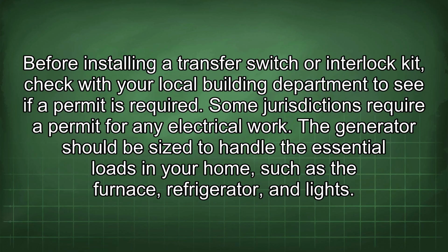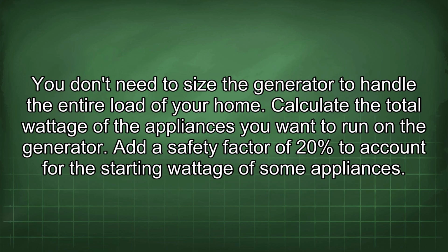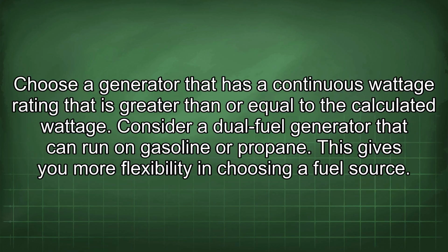Before installing a transfer switch or interlock kit, check with your local building department to see if a permit is required. Some jurisdictions require a permit for any electrical work. The generator should be sized to handle the essential loads in your home, such as the furnace, refrigerator, and lights. You don't need to size the generator to handle the entire load of your home. Calculate the total wattage of the appliances you want to run on the generator. Add a safety factor of 20% to account for the starting wattage of some appliances. Choose a generator that has a continuous wattage rating that is greater than or equal to the calculated wattage.